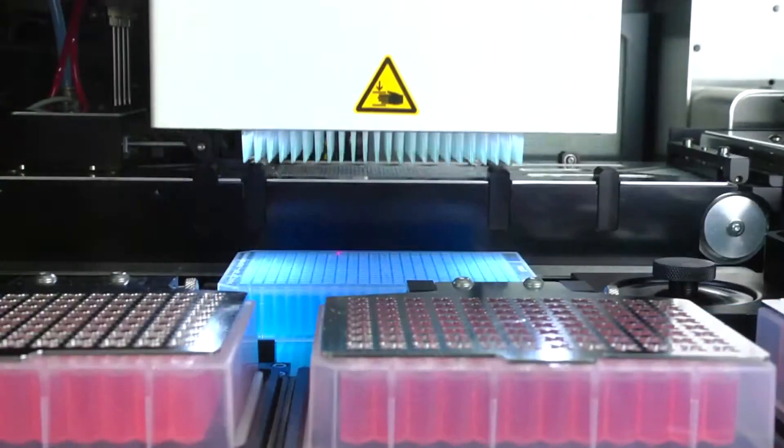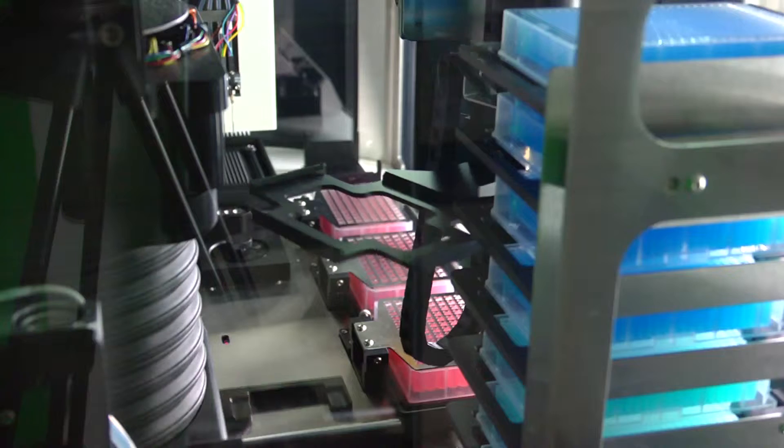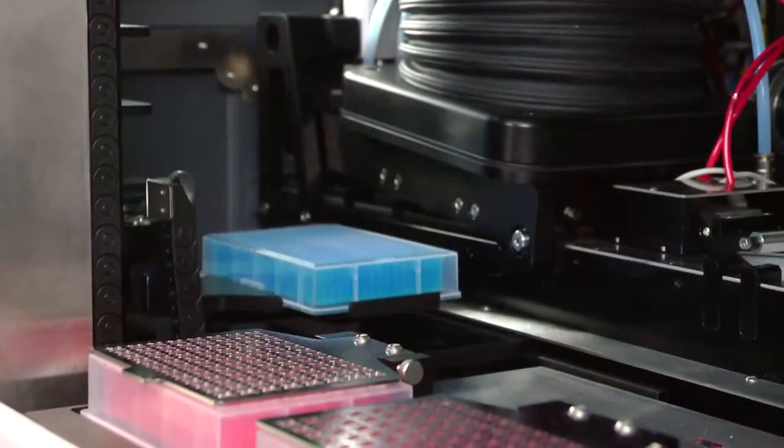The process begins with independent aspiration of the DNA sample and reagents from their respective source plates. Source plates can be randomly accessed through the plate stacker located on the instrument.